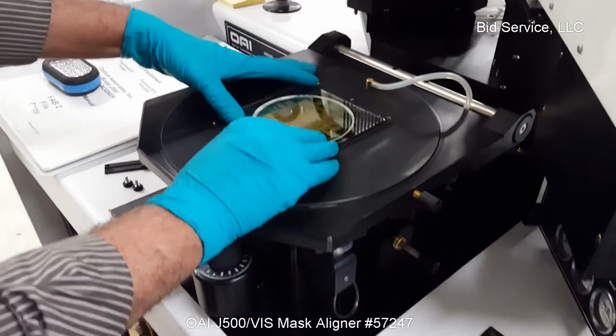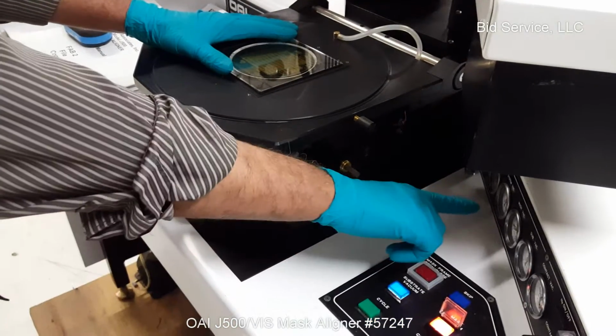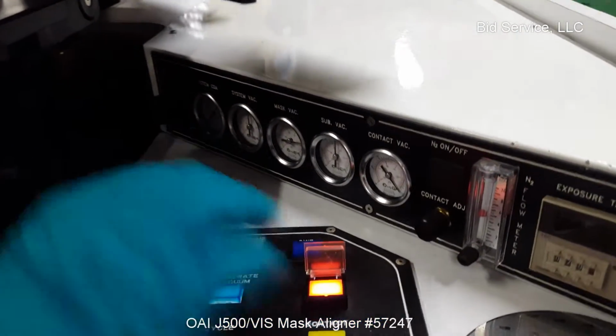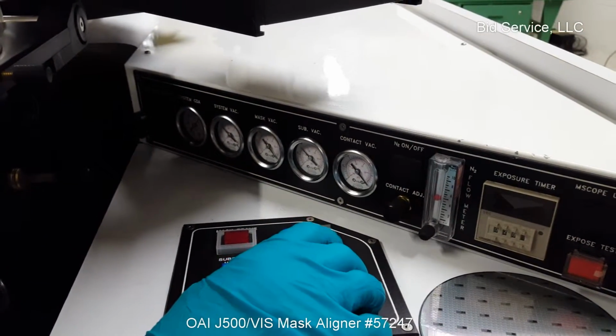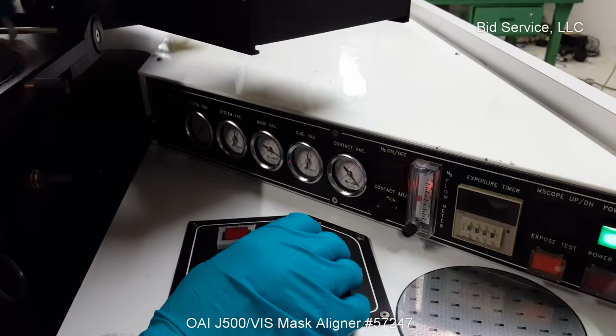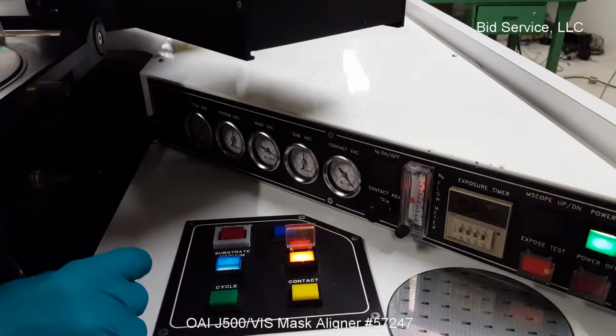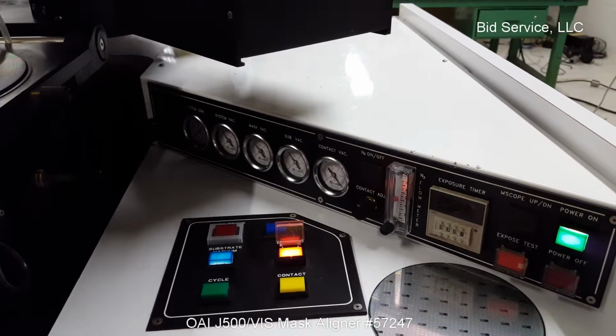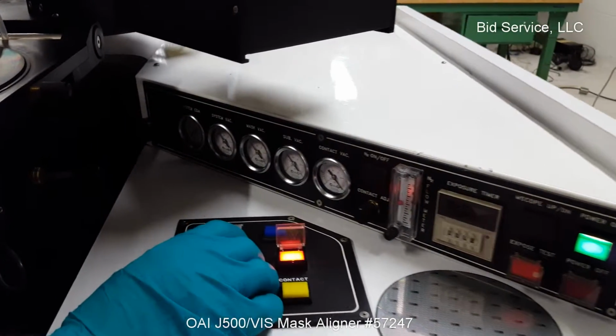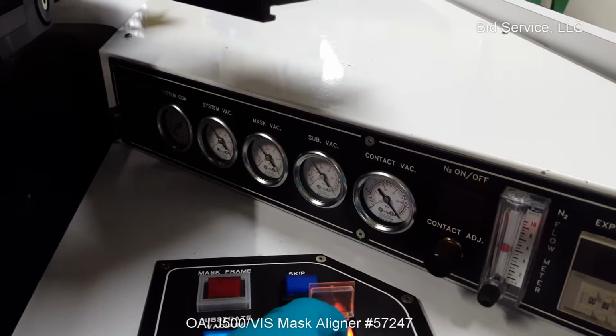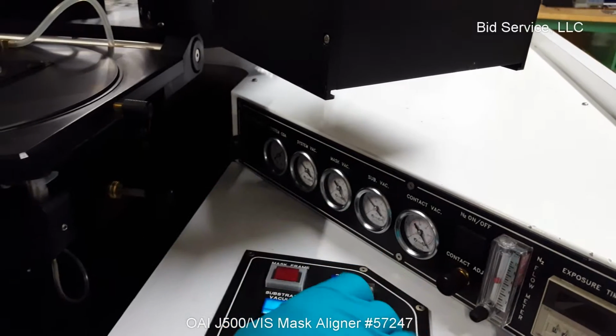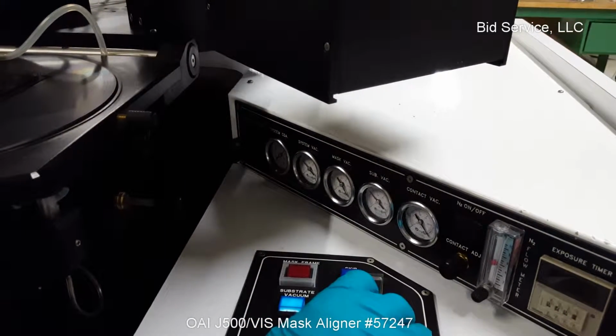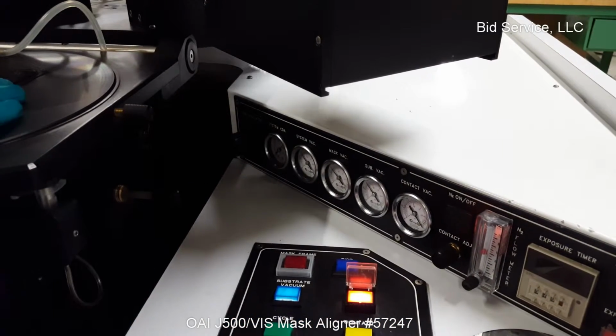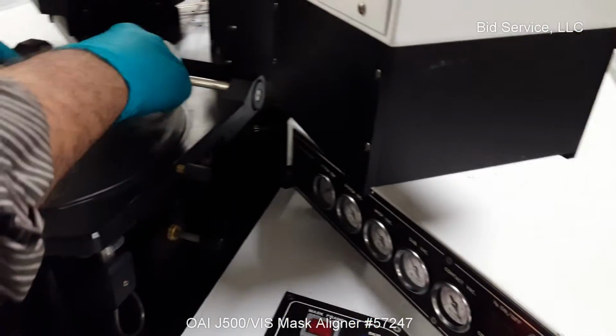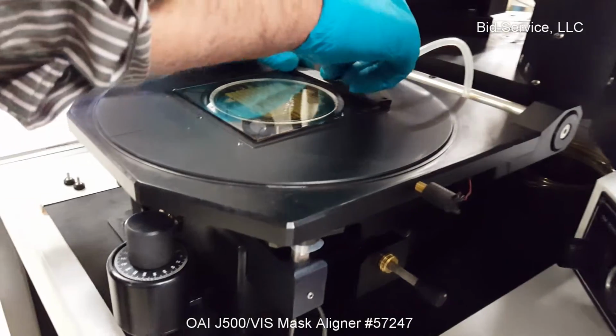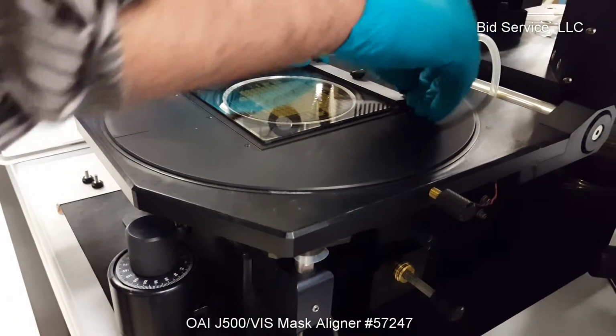So when you turn on the mask vacuum, you have to check the mask vacuum meter, so that it should be close to the system vacuum level. If it is not equal, that means there is some leak. So now it is good. Turn it off. The system vacuum is about 25 inches of mercury. And I turn on the mask vacuum and the vacuum level approaches 25 inches. Just to secure the mask, these brackets have to be connected using the thumb screws.